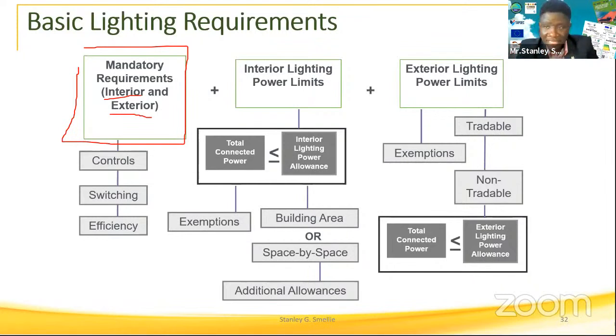So you talk about lighting power density and how you use that information to ensure conformance. The standard has a lot of tables with details about lighting power density for facilities of various types. You can approach it under interior light limits, in terms of building area, or space by space. Some organizations have cubicles, a large auditorium with cubicles, others have individual offices, and many different configurations. The code considers all of that, with tables providing the information you need to ensure your lighting design, when finished, will be in conformance with the standards, as long as you implement the various requirements.